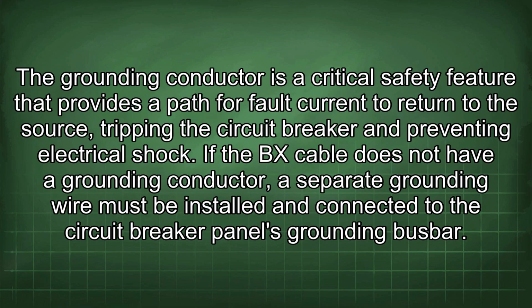The grounding conductor is a critical safety feature that provides a path for fault current to return to the source, tripping the circuit breaker and preventing electrical shock. If the BX cable does not have a grounding conductor, a separate grounding wire must be installed and connected to the circuit breaker panel's grounding bus bar.